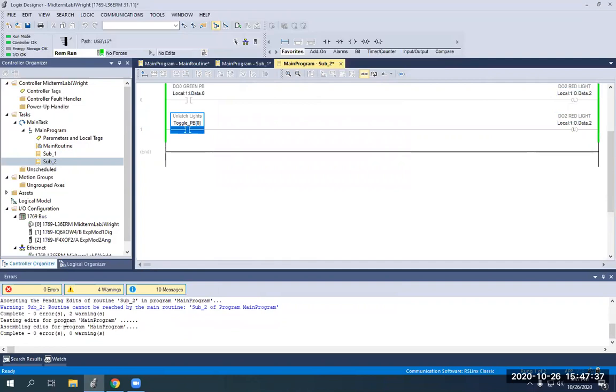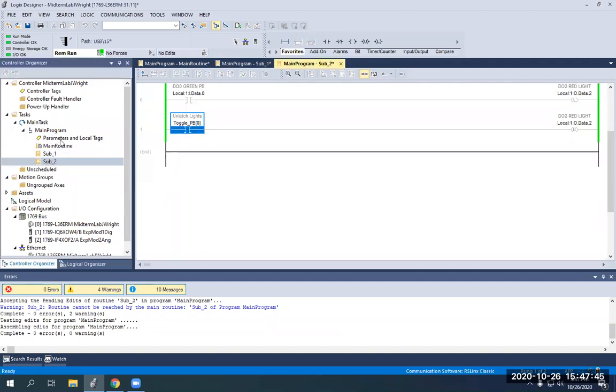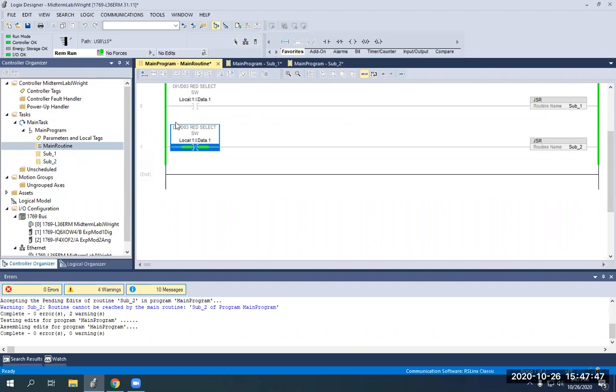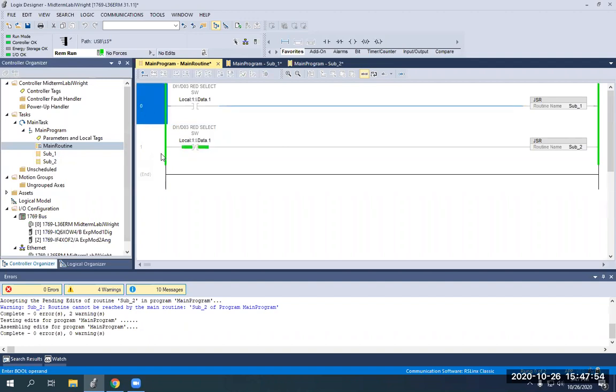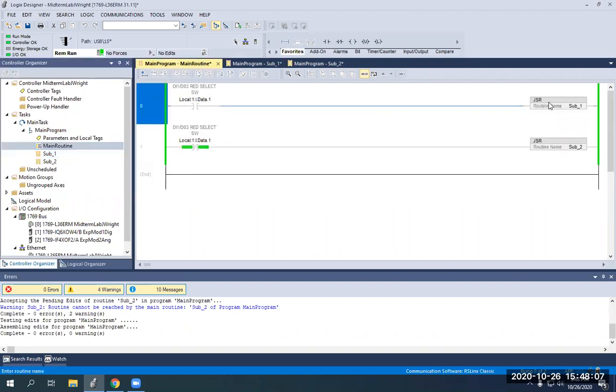So now we just finalized all of our rungs and routines — we're finalized in sub two and finalized in the main routine. Basically what's going to happen here is according to the program the way it's set up, we can use subroutine two, but subroutine one is useless. So if we go into subroutine one and I push the green push button, nothing will happen because in the main routine our JSR — our jump to subroutine — is not getting energy to it. It's not energized.